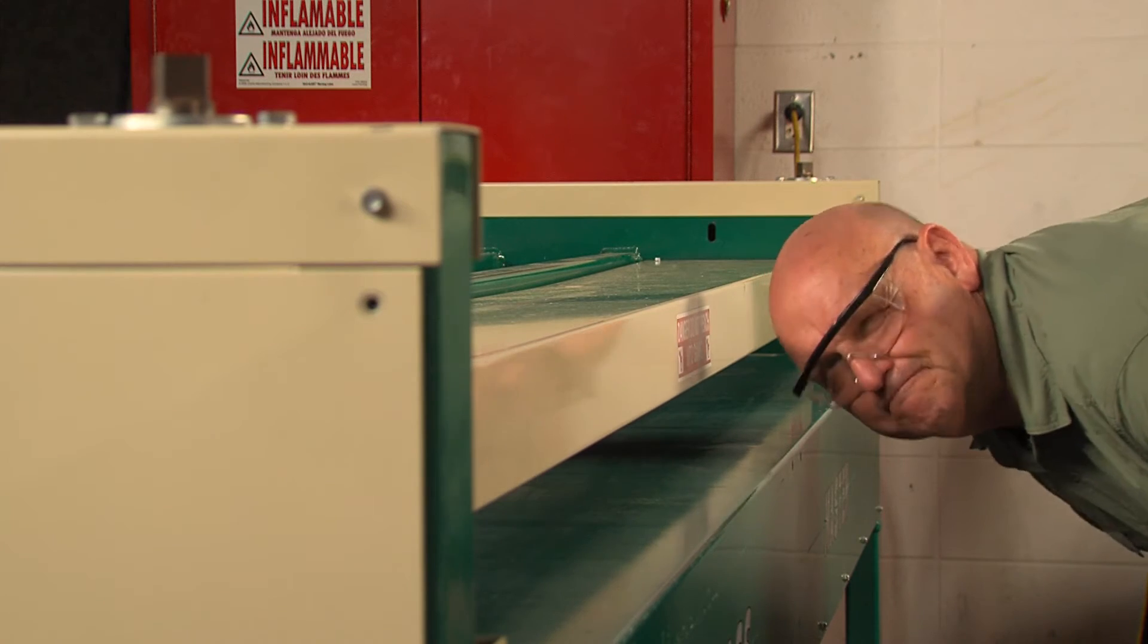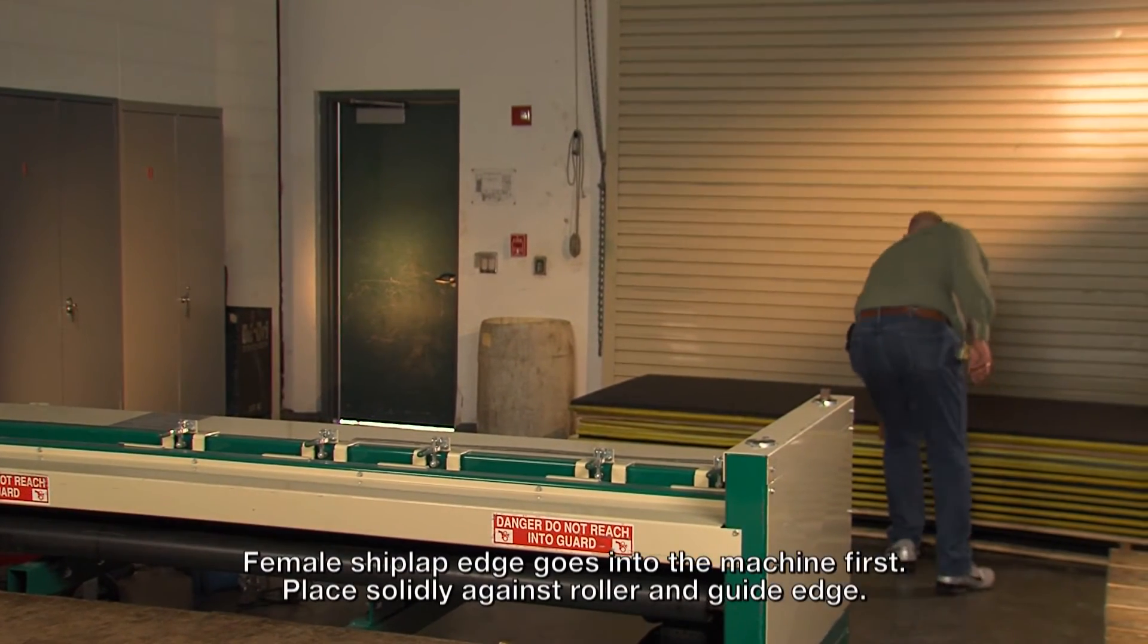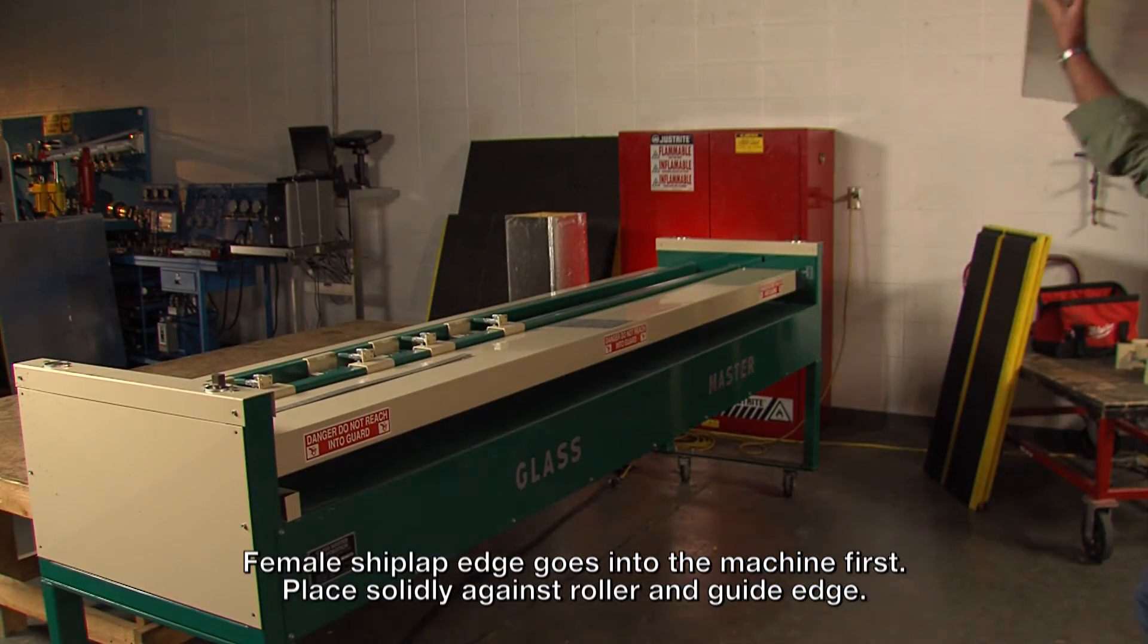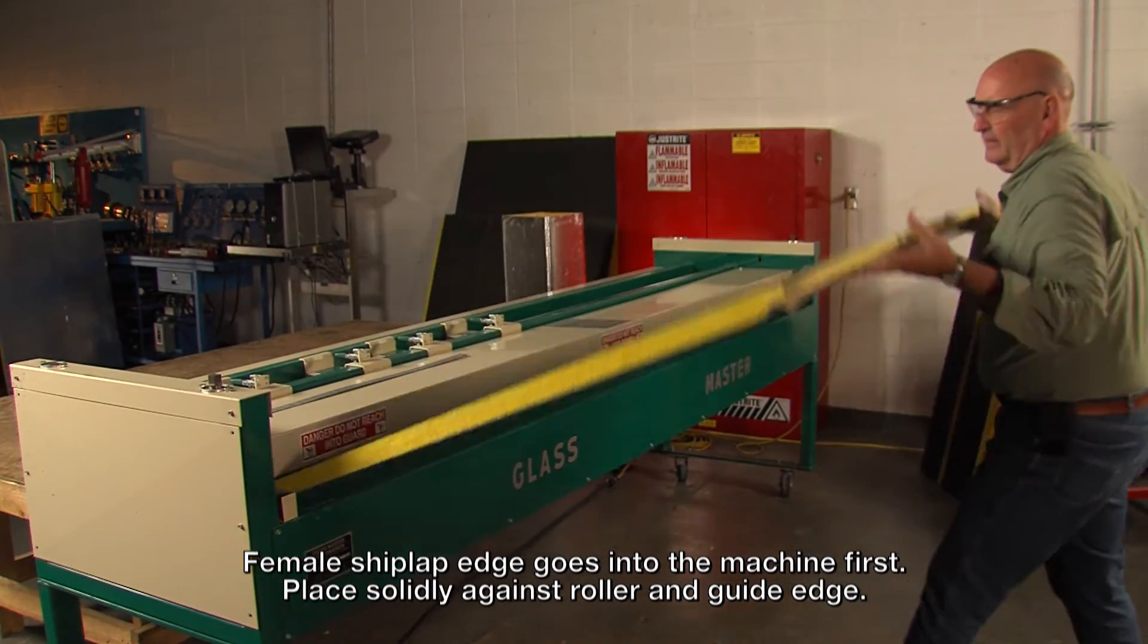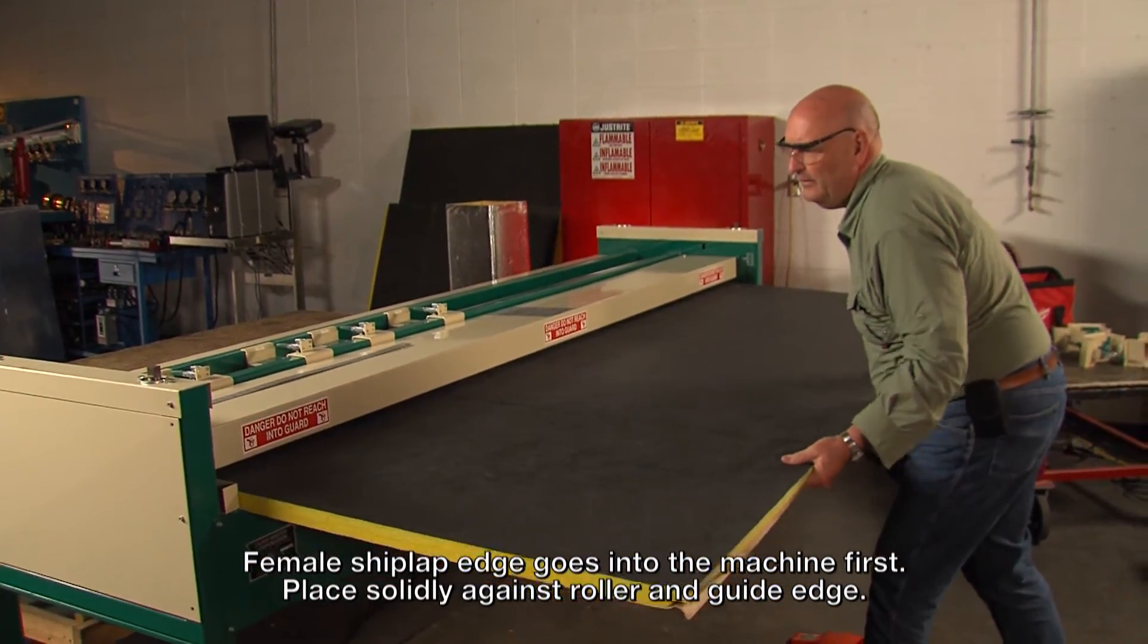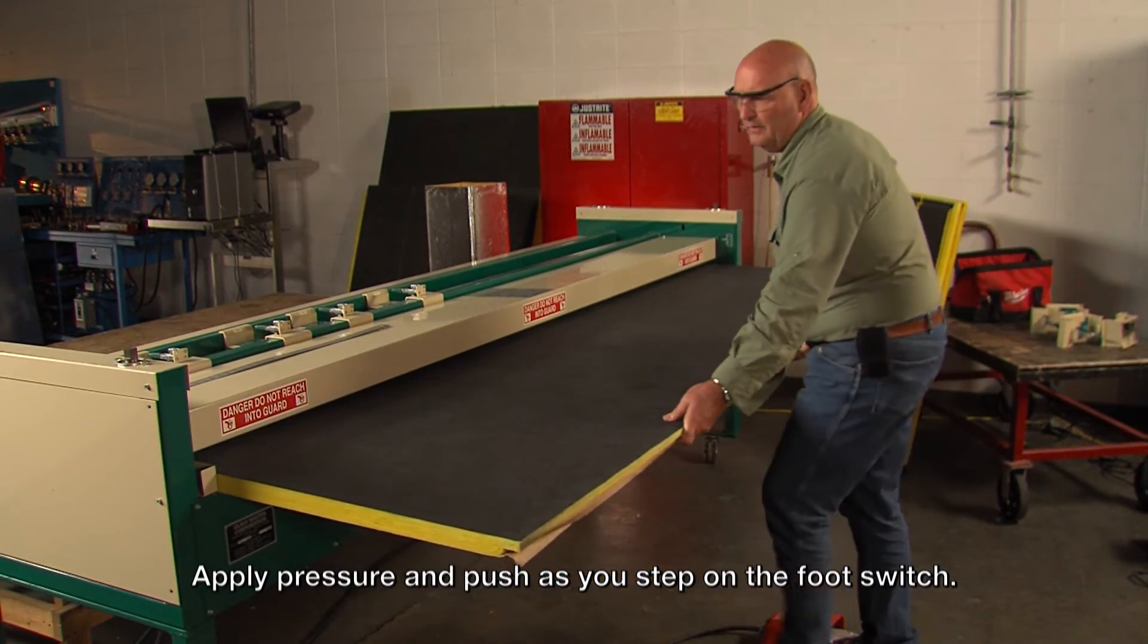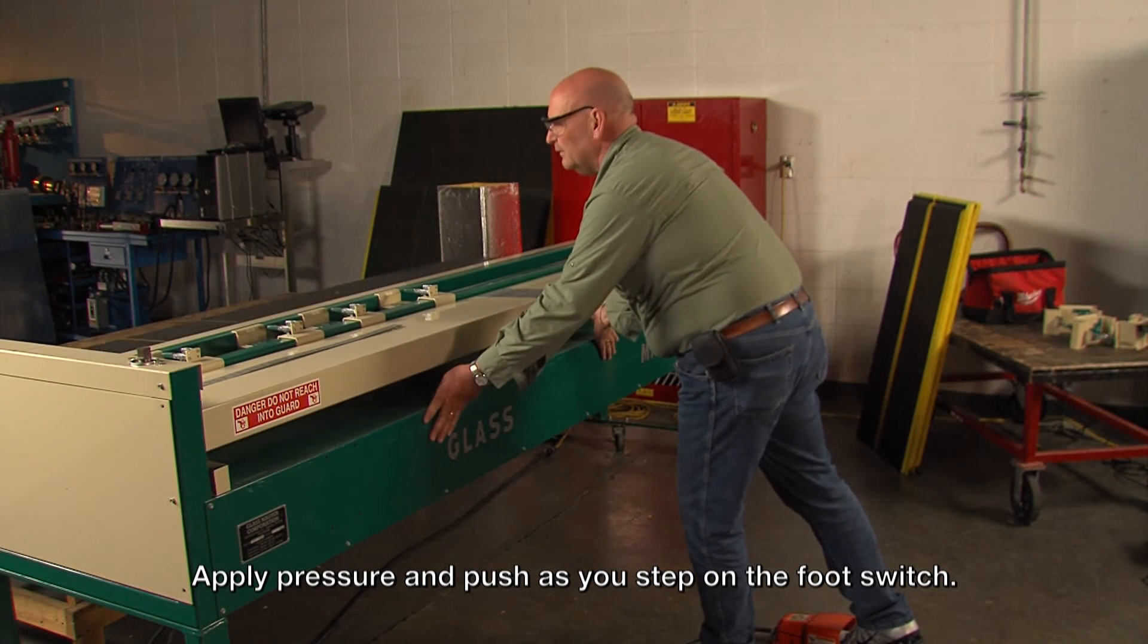Now we are ready to groove the duct board. Note that the female shiplap edge goes into the machine first. The female shiplap edge is pushed in solidly against the roller while the left edge is up against the left side guide. Turn the machine on forward, apply pressure or push the board with both hands in the direction of the machine, and step on the foot switch.